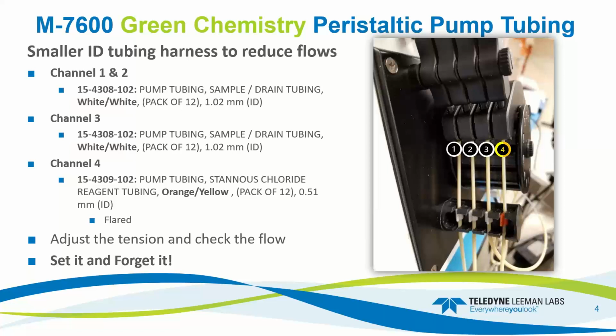So to accomplish our goal, we experimented with various configurations and trials that ultimately maintain the same reagent to sample ratio while reducing the inner diameter of the tubing set. So we chose a peristaltic pump harness that is identical to the standard setup, except we're swapping in a smaller internal diameter tubing to reduce waste generation.